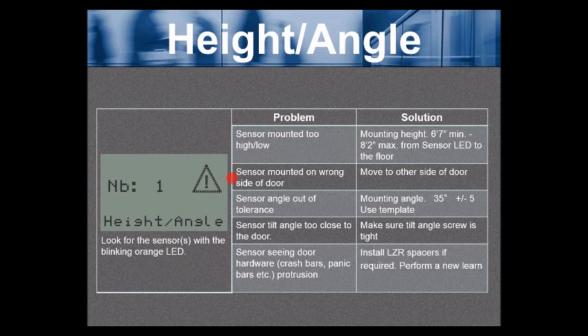The next most common problem with the height angle error is the sensor is mounted on the wrong side of the door. Move the sensor to the other side of the door. And what you'll see on each sensor is a little red arrow. The arrow should be pointing toward the hinge.